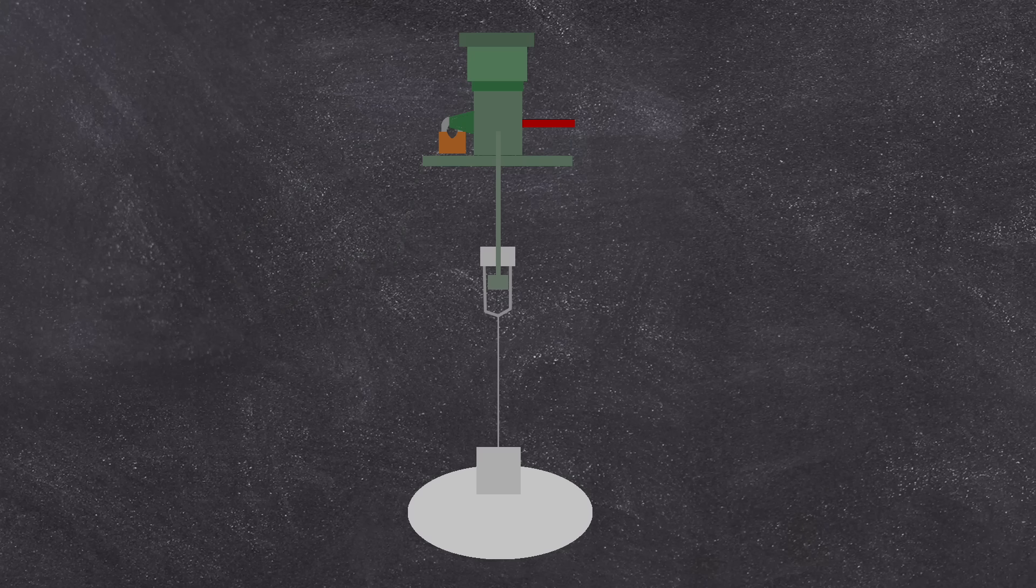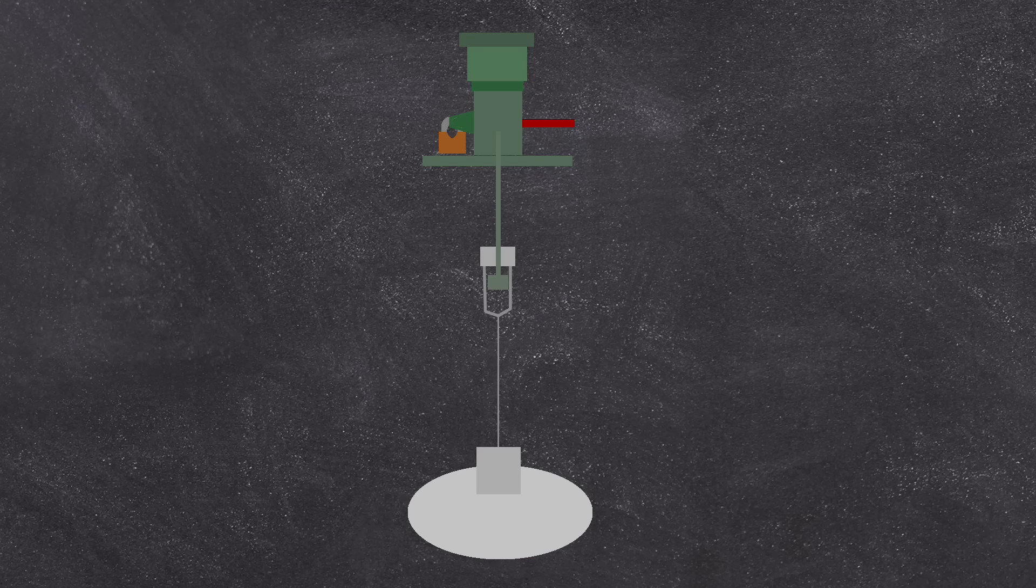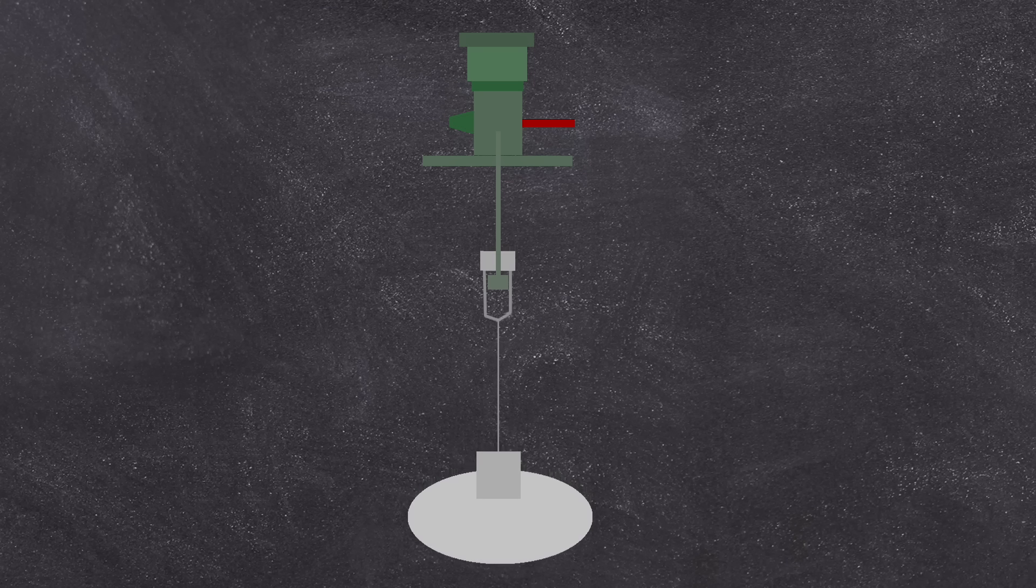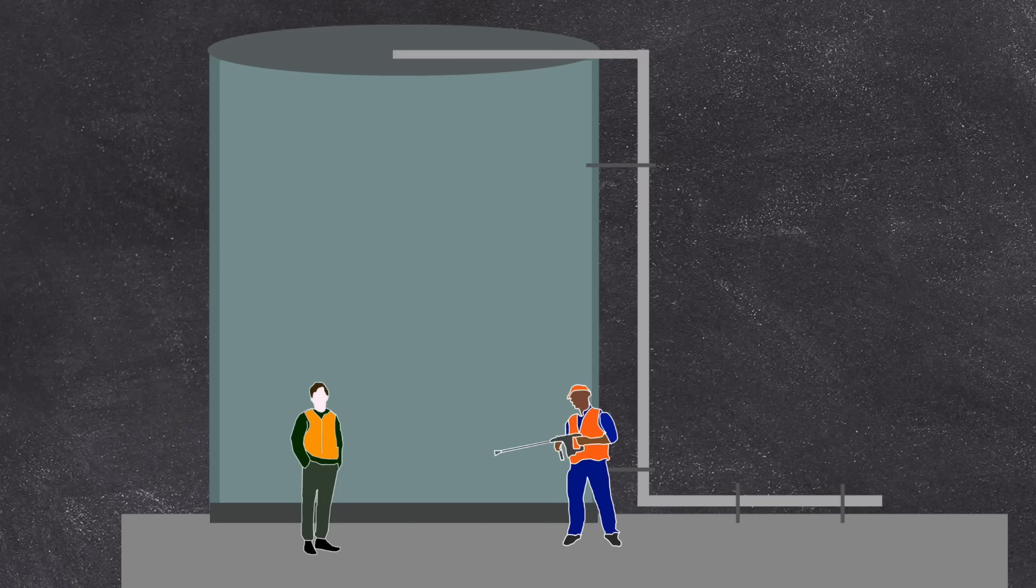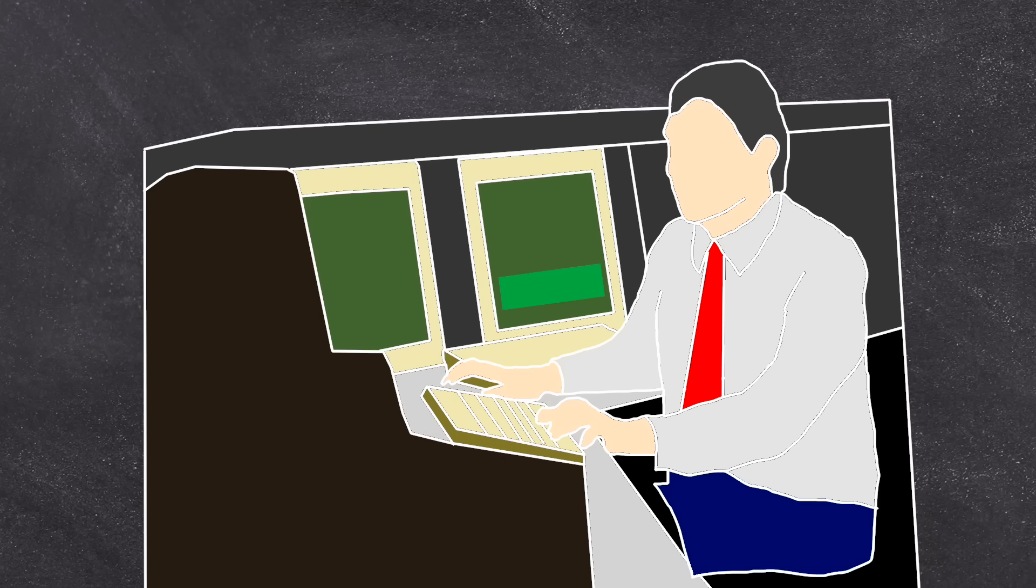This would keep the lever in the middle position during normal operation. However, operators needed to do regular system checks. To do this test, they had to remove the padlock to push the lever into the upward position for testing out the alarm. However, it was found that after a test, the padlock had not been replaced, thus allowing the lever to go into the lower position, disabling the automatic shut off. Operators didn't know about the strange design quirk in this system. So now then, what of the gauge and its freezing during filling? Well, apparently this was a known issue since the tank had been serviced earlier in 2005, but no one thought to chase this up and log the fault. Instead, they relied on the independent system preventing an overfill, which we now know was accidentally disabled.